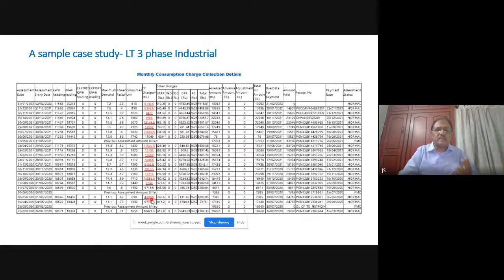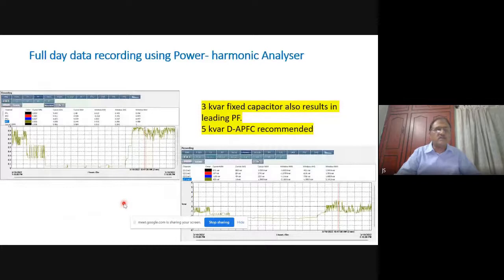It is a single shift industry, or a general shift industry. During the nights, they don't have any load, and they have one naked lamp only in the nights, and the power factor is very, very poor. So what we did was, we did a small survey. These are leading power factors, as you can see here, minus, these are all leading power factors. So we did a small survey, again, for one day. And then we found out that we connected a fixed 3 kVAR, even that was resulting in a leading power factor.